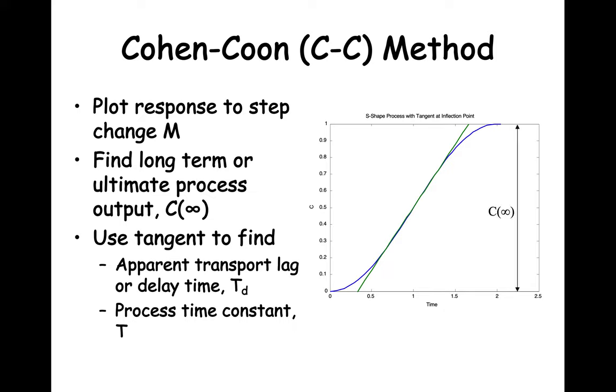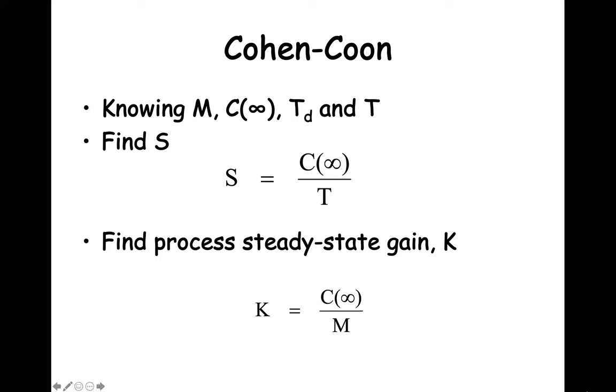Then we find the apparent transport lag. The transport lag Td is the time between time T equals 0 and the time when the tangent crosses 0 output. The next thing to find is the process time constant T. The process time constant is the time between when the tangent crossed 0 and when it crossed C infinity. Now that we know M, C infinity, Td, and T, we can calculate the tangent line slope S, where S equals C infinity over T. We can also calculate the process steady state gain K, which is C infinity over M.